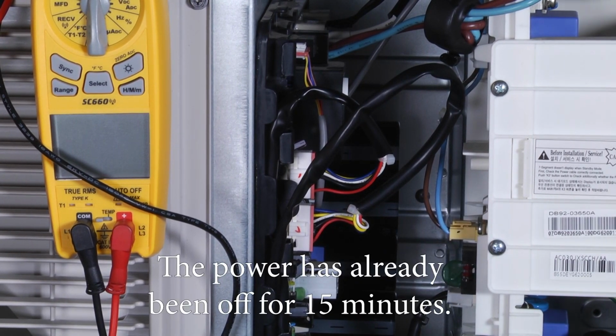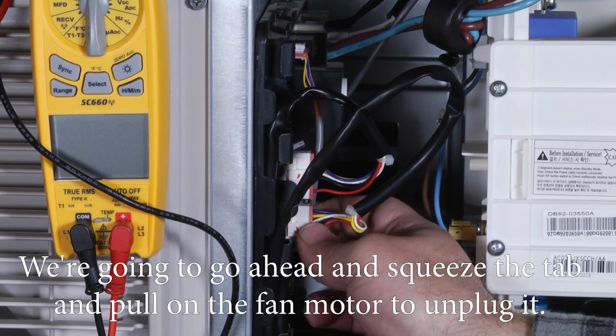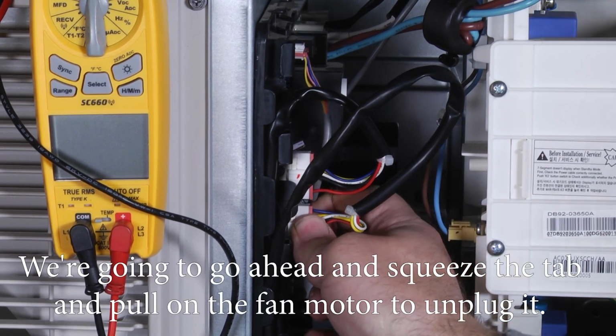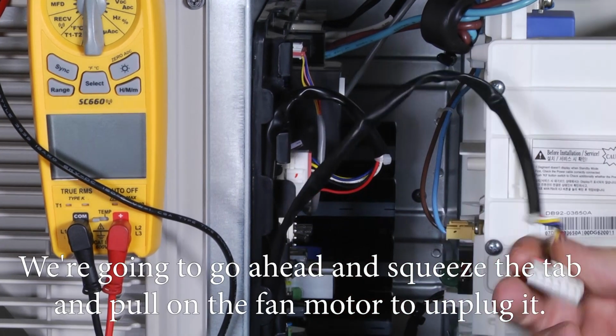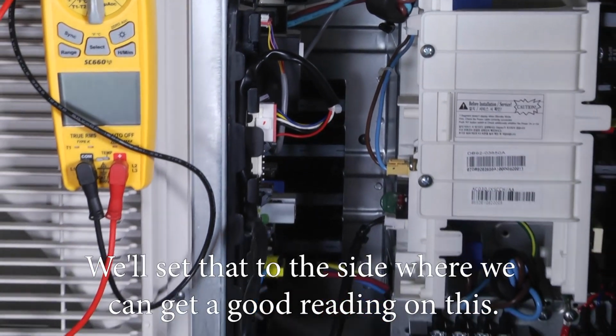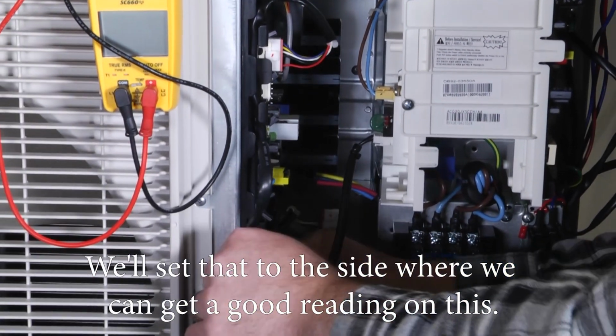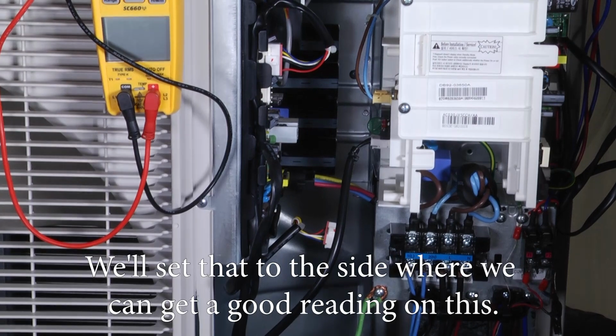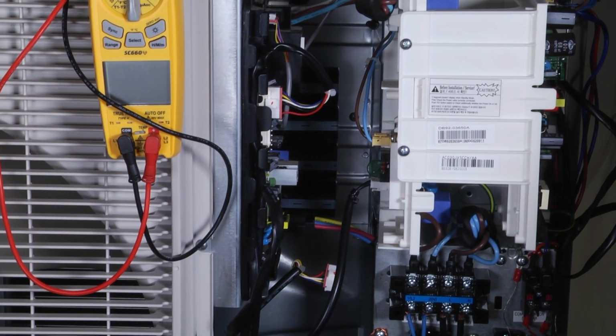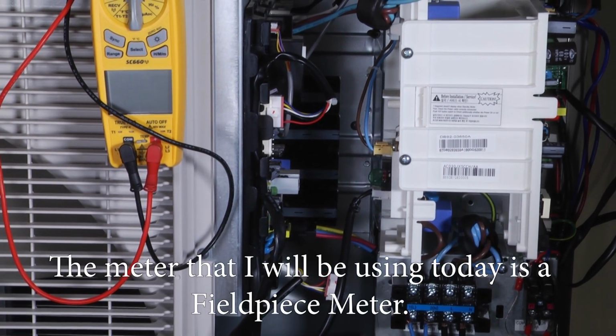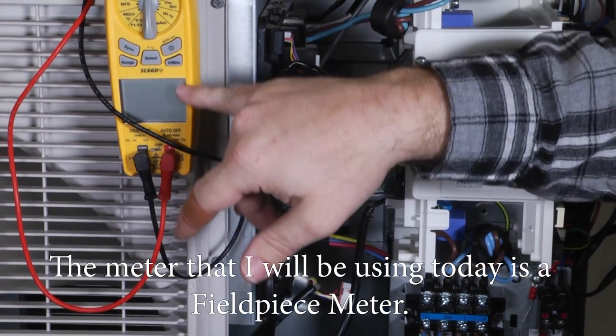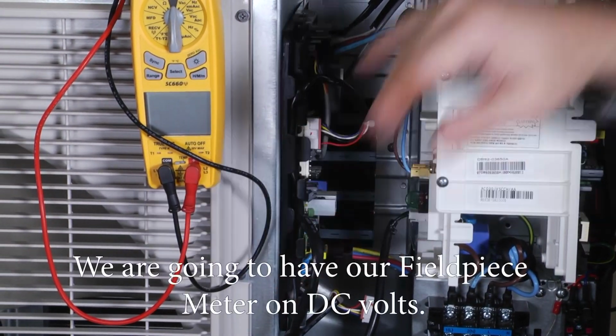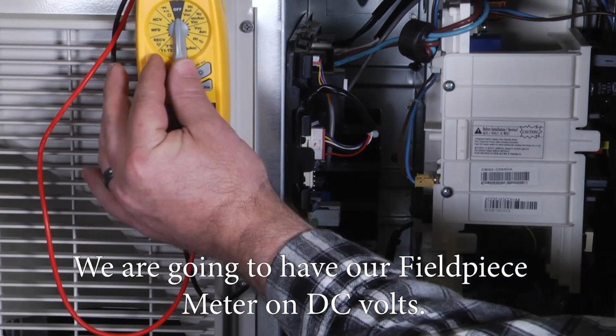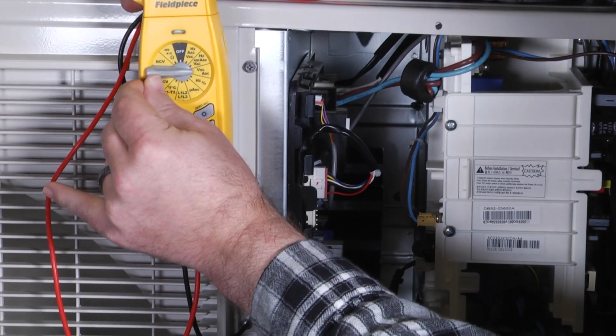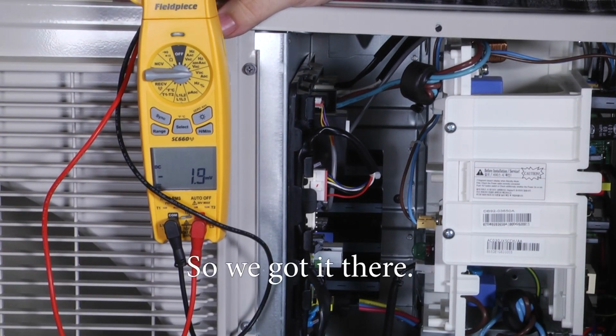So the power has already been off for 15 minutes. We're going to go ahead and squeeze the tab and pull on the fan motor to unplug it. Kind of set that to the side where you can get a good reading on this. The meter that I'll be using today is a Fieldpiece meter. We're going to have our Fieldpiece meter on DC volts. So we got it there.